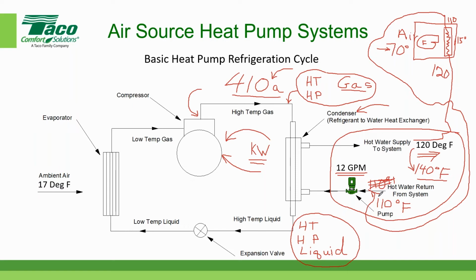So anyway, hopefully that answers the question. We're sending it out. We're just going to erase this for now because that's later. We're sending it out at 120 degrees, and we have some type of terminal device. In this case, I've demonstrated a fan coil: F for fan, C for coil, that's fan coil. It could be radiant floor heating. It could be special low temperature convection heaters or cabinet heaters. All kinds of equipment that's now available that runs on low temperature supply water to provide as much heating capacity as possible.